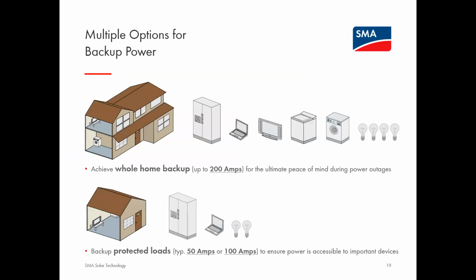So when it comes to the backup power use case, there's basically two ways that you can integrate the backup into the home. First and foremost is the category of whole home backup, where we have up to 200 amps pass-through available in the automatic backup unit. In this scenario, you really can back up most of the major loads and appliances in a home, including microwaves, refrigerators, large appliances, washer dryers, as well as those creature comforts, lighting, entertainment, and so on.